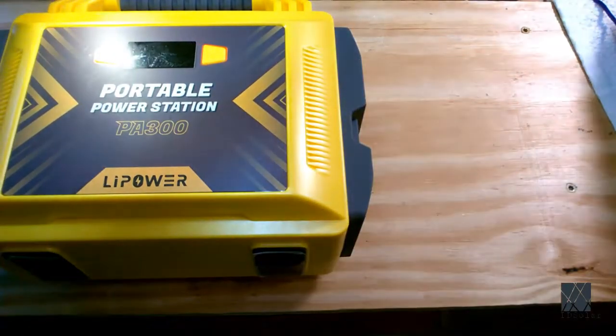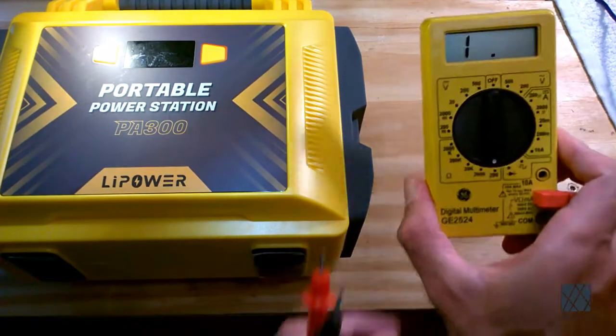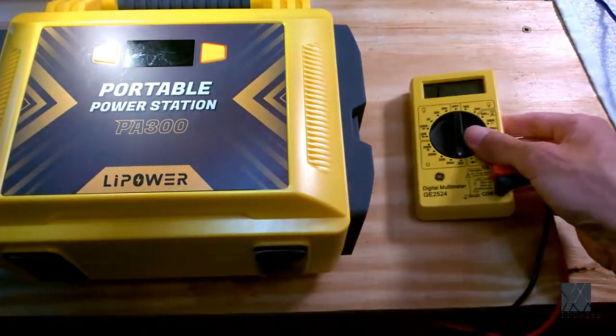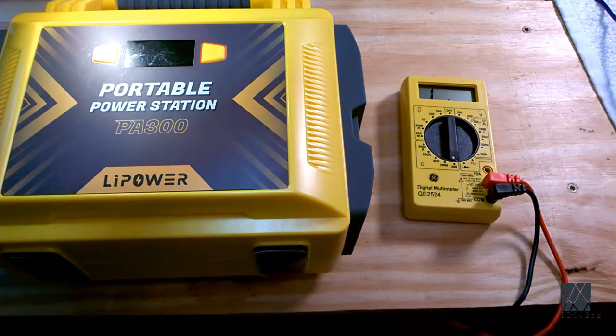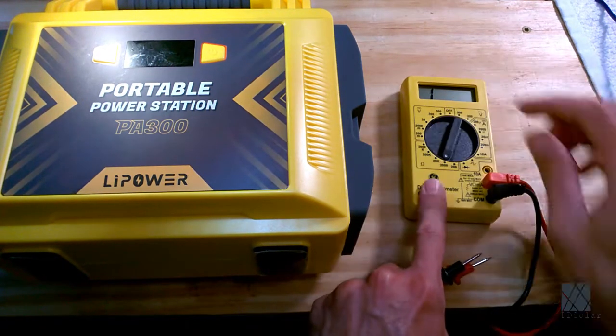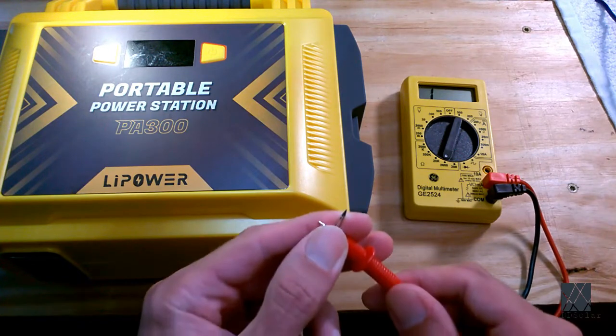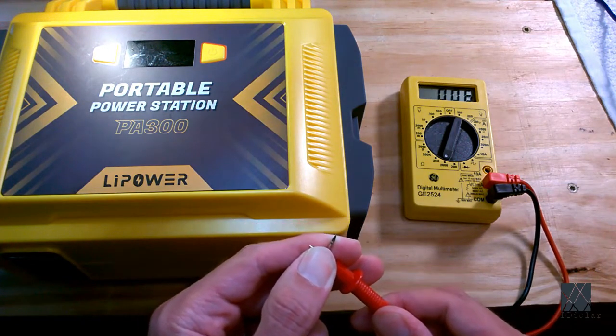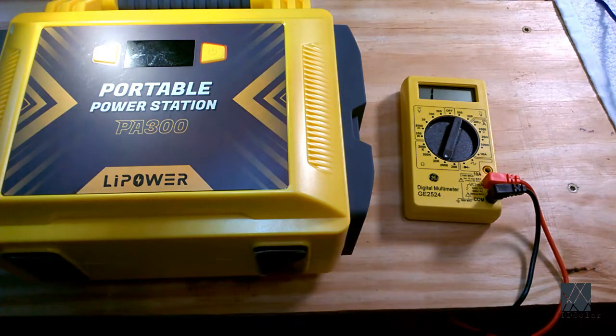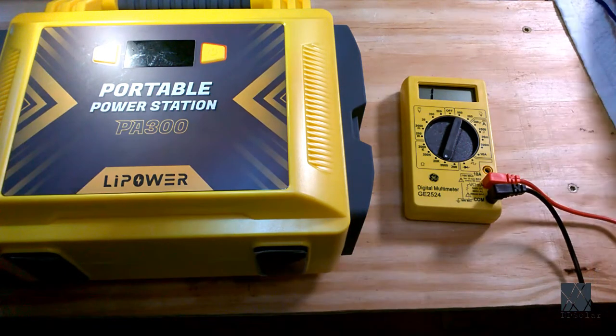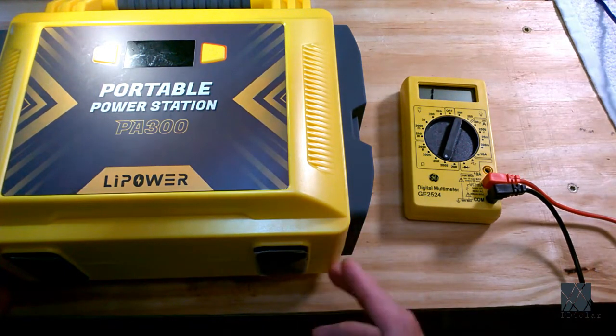Next thing I would do, usually, I want to check the outputs and inputs. So I'll usually set an ohm meter on maybe 200 ohms, and actually I'll make it 2000. The ohm meter is just going to measure resistance, and one of the first things I want to do is see if any of the inputs and outputs on this thing are shorted.